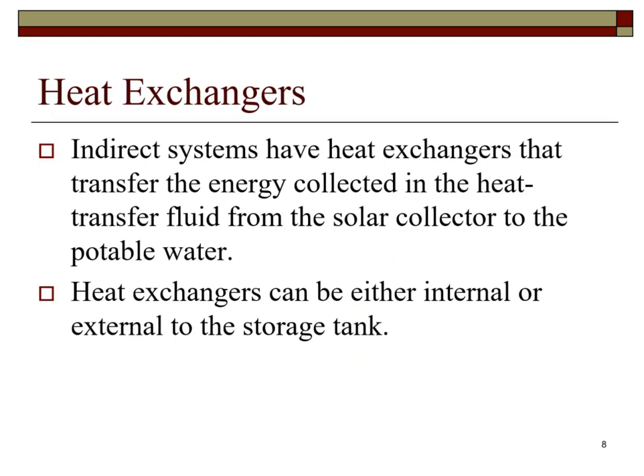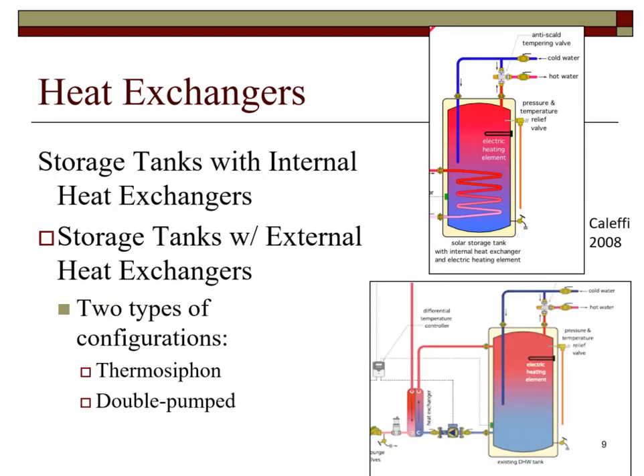Indirect systems have heat exchangers which transfer the heat from the heat transfer fluid to the potable water. The heat exchanger can be either internal or external. The upper tank has an internal type heat exchanger. The lower tank has an external flat plate heat exchanger. The internal heat exchanger requires only 1 pump. The external heat exchanger may require 2 pumps or may have 1 pump to the solar thermal module and depend upon thermosiphon to circulate the water through the second storage tank.